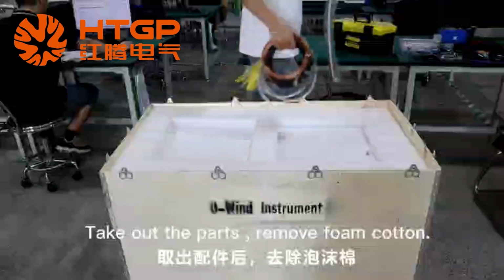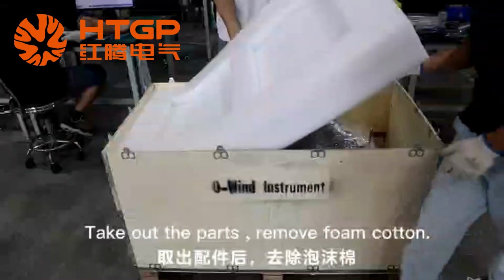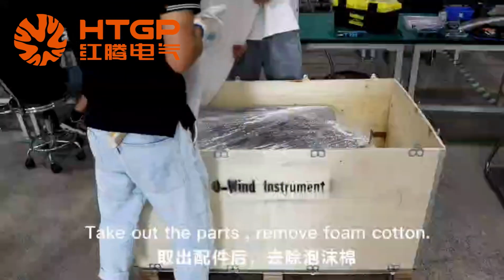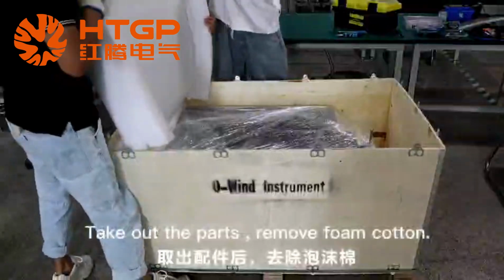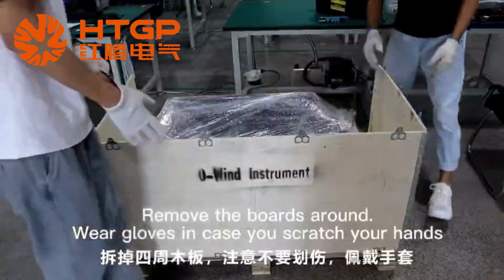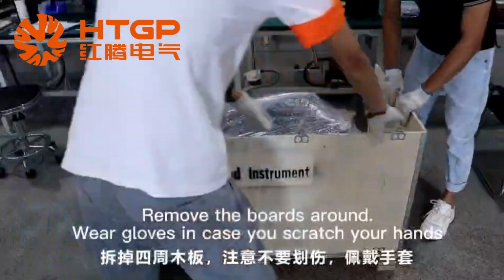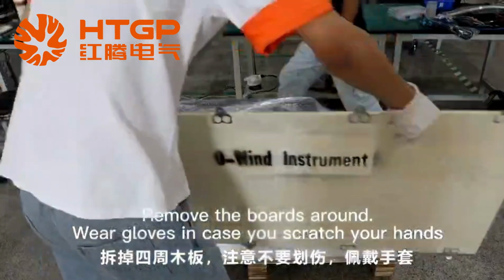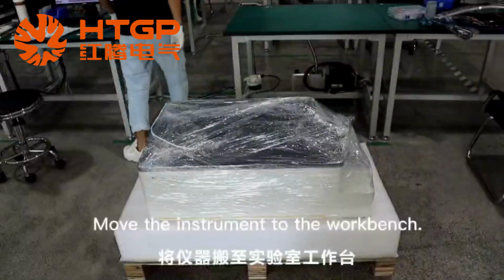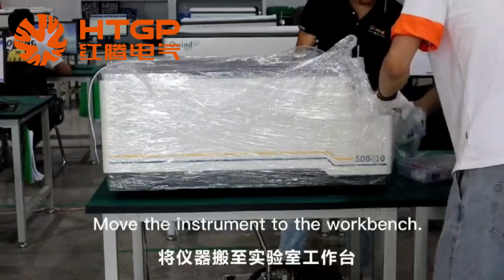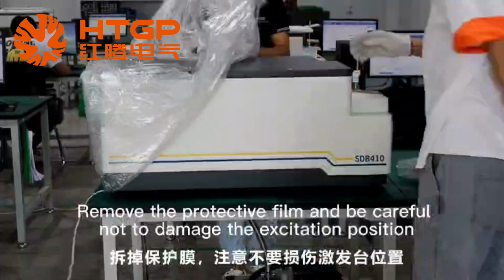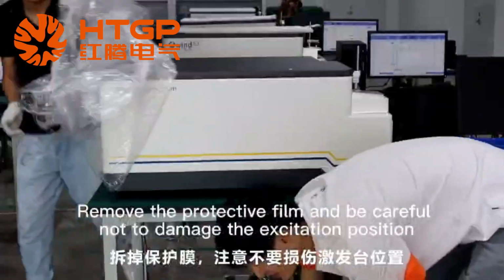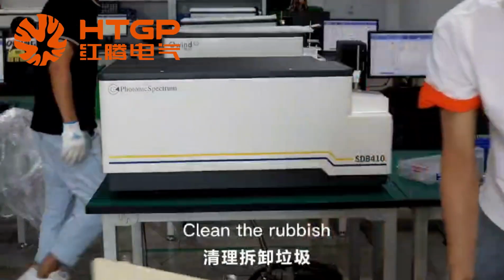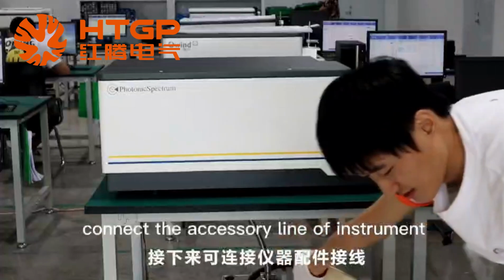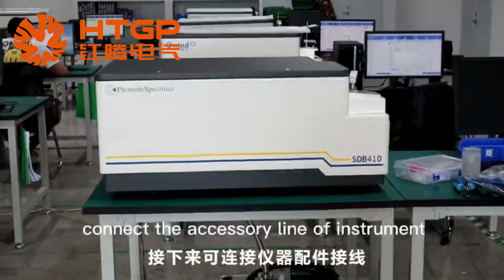Take out the parts, remove foam cotton. Remove the boards around. Wear gloves in case you scratch your hands. Move the instrument to the workbench. Remove the protective film and be careful not to damage the excitation position. Clean the rubbish. Connect the accessory line of instrument.